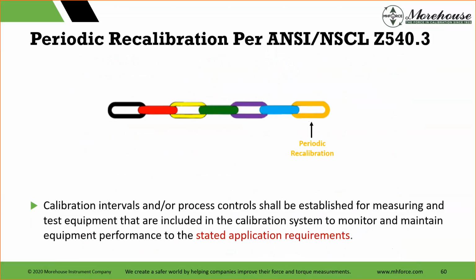One of the reasons why we're in business is calibration intervals or process controls shall be established for measuring and test equipment that are included in the calibration system to monitor and maintain equipment performance to the stated application requirements. So have your equipment calibrated, calculate, is it drifting out, monitor that, use control charts if you can. Get that test cell, that check standard, 5-in-1 kit, some people call them, or we've called them that, where you can do 5 things with one. You can satisfy a lot of the criteria for ISO IEC 17025.